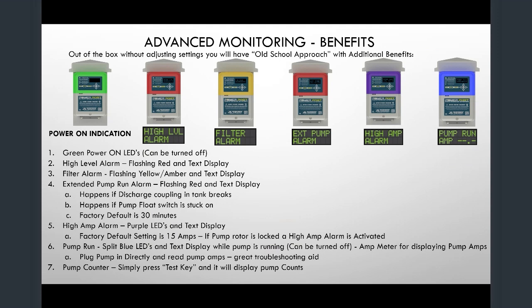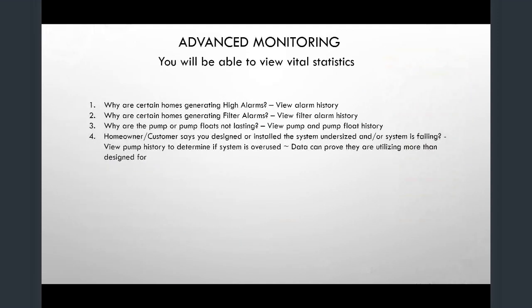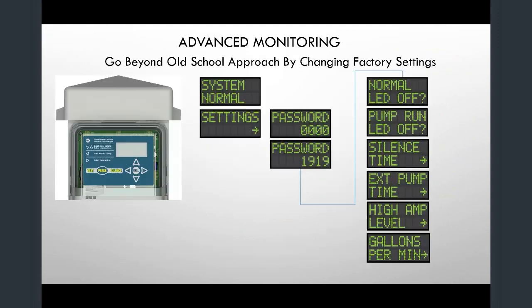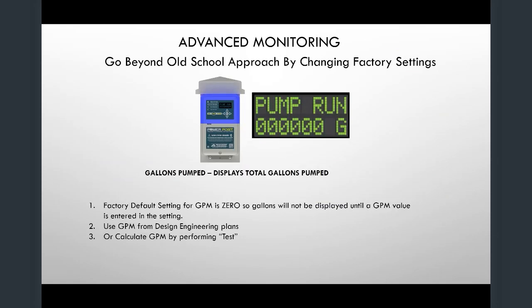And then also the blue would be the pump run. We also have an indigo or a white one for, I forget what those are for. I don't show these here. Just kind of goes into it. And then it also goes into showing you if you have power losses. You can go in here if you want and establish how many gallons per minute your system pumps out. And then we can do a totalization, tell you how many gallons you pumped for your system.